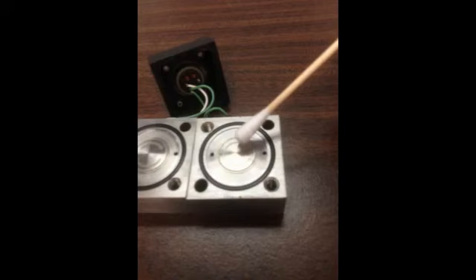Also inspect the inside of the sensor cavities for any trace of dirt, grit, or other contaminants. Even a small particle can keep the sensing diaphragm from moving and the transducer from responding to pressure. The inside of the sensor cavities should be cleaned with alcohol and a cotton swab before reassembly, even if you cannot see any dirt.